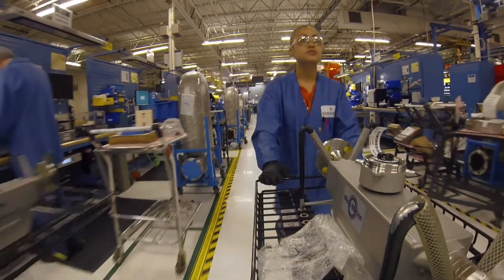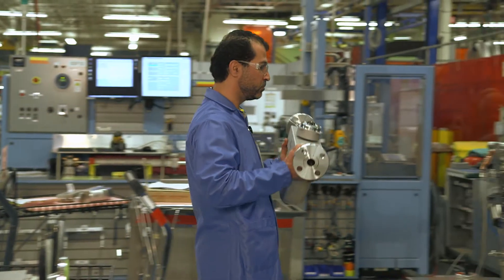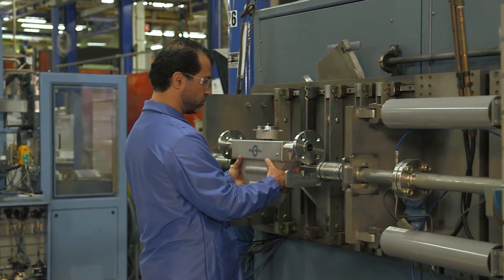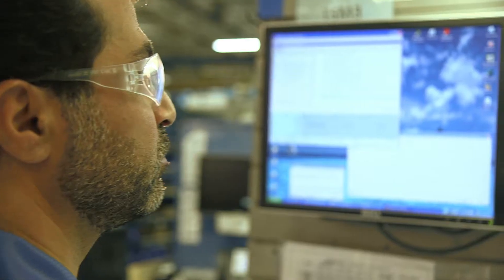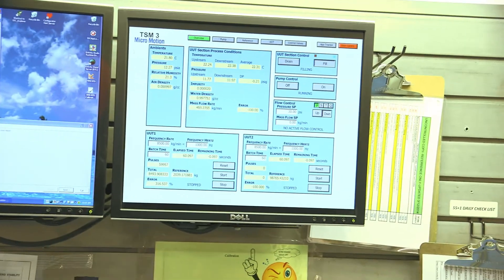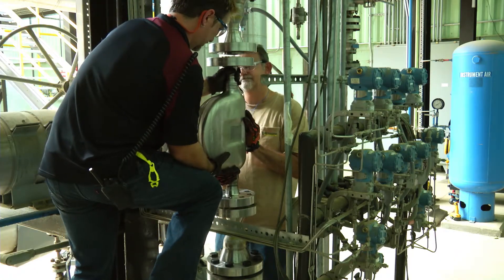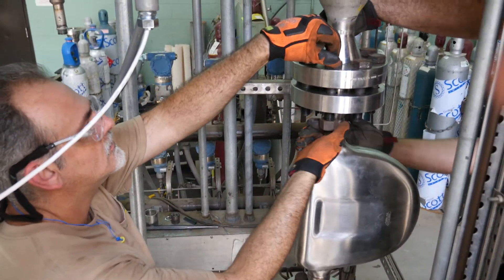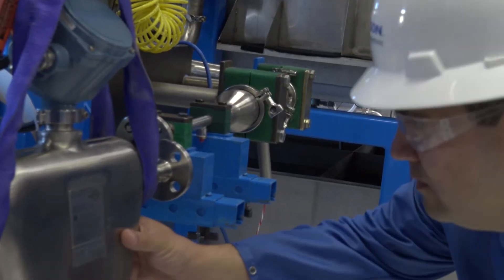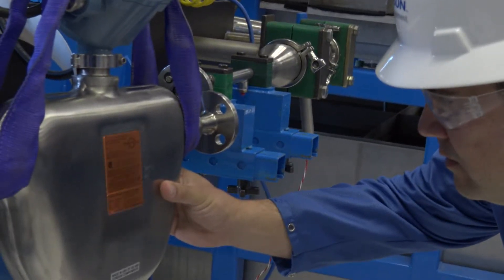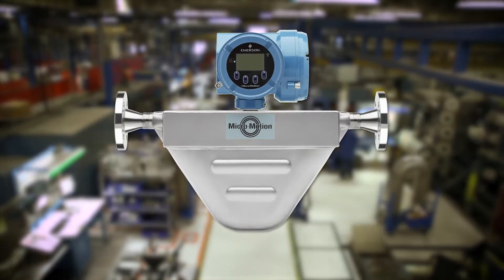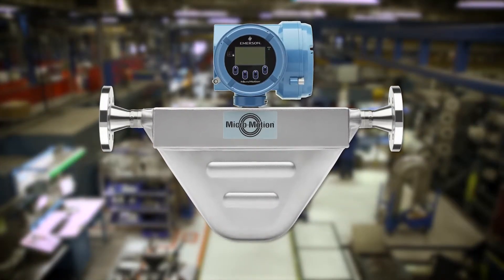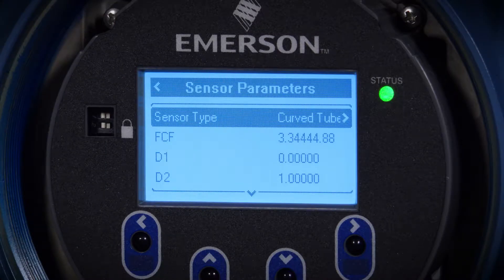Characterizing the meter adjusts the meter electronics to match the unique traits of the sensor it is paired with. The characterization parameters describe the sensor's sensitivity to flow, density, and temperature. Depending on your sensor type, different parameters are required. Values for your sensor are provided by Micromotion on the sensor tag or the calibration certificate. If your transmitter was ordered with a sensor, it was characterized at the factory. However, you should still verify the characterization parameters.